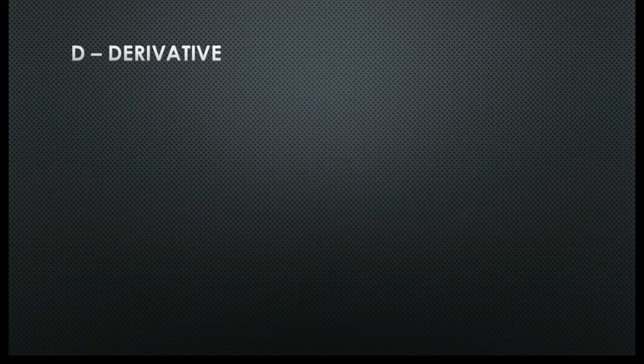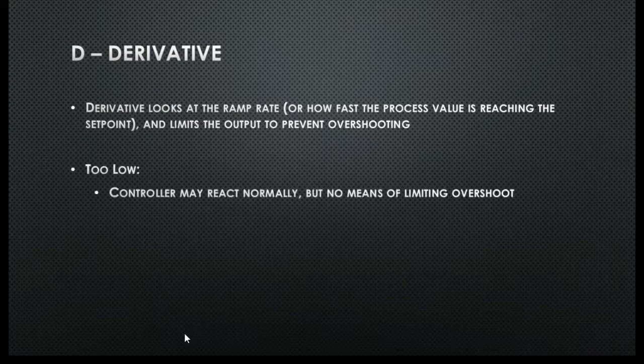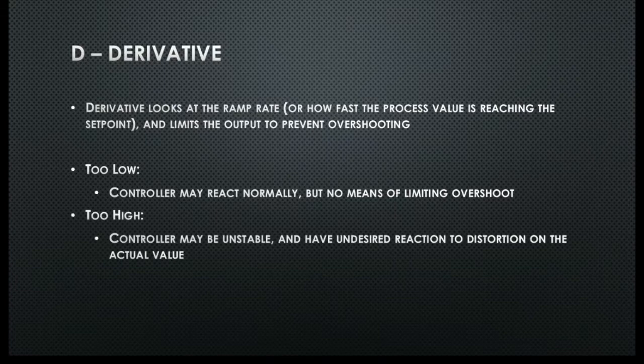Now for the third and final portion of our PID controller — the D, or derivative. The derivative is one of the most misunderstood parts of the PID controller. But when put simply, it is just looking at the ramp rate of the process value, and if it sees that it's going to be overshooting, then it pulls back on the output to try and prevent that overshoot. If the derivative is set too low, the controller may act normally as with a PI controller — but if you need a faster reaction and need to set the P and I higher, you have no way of limiting overshoot with too low a D value. If the derivative is set too high, the controller may become unstable and have an undesired reaction if there's any distortion on the loop that makes the ramp rate look faster than it is.